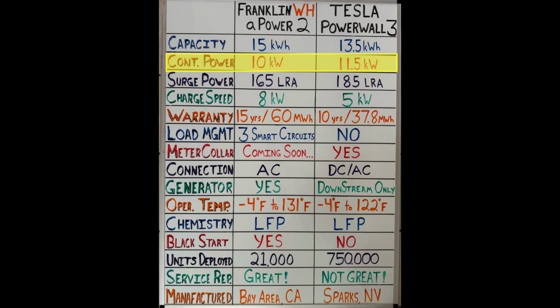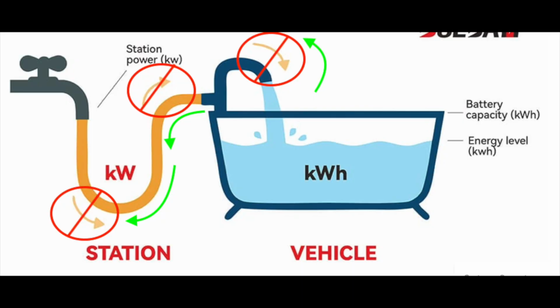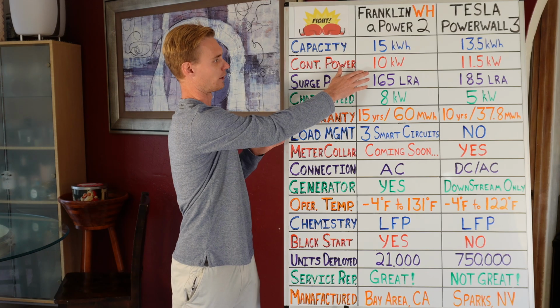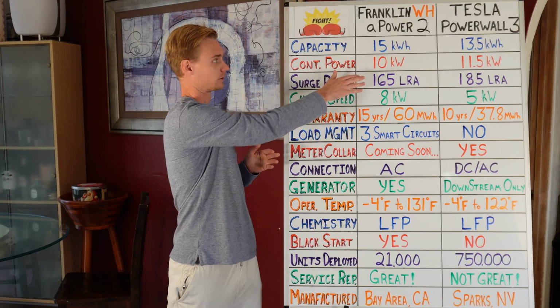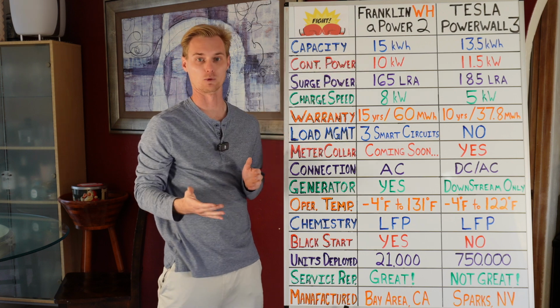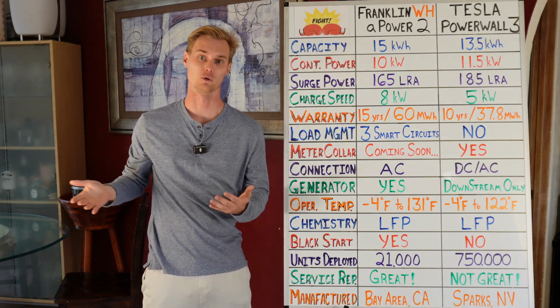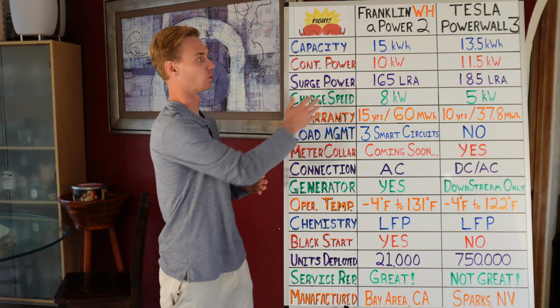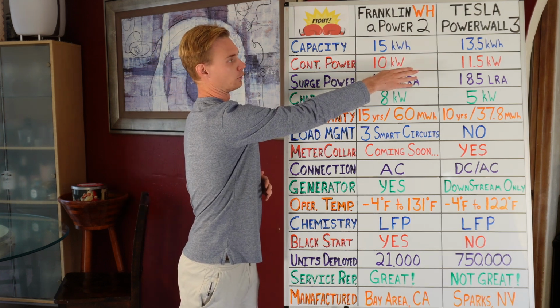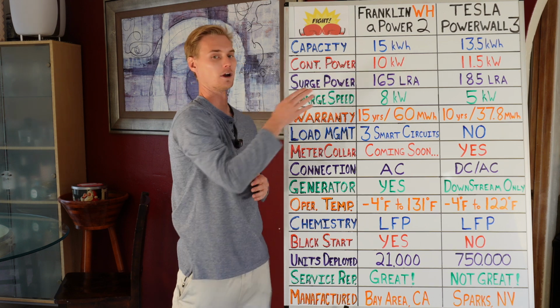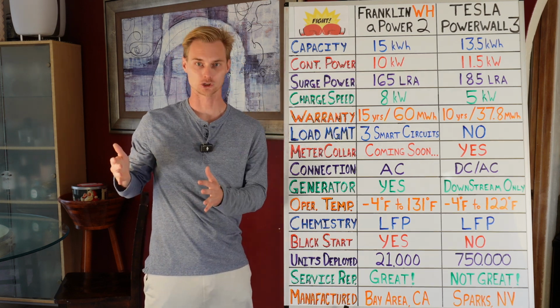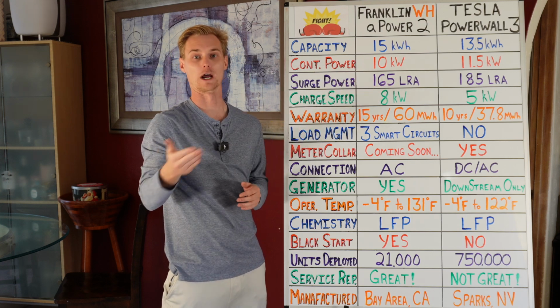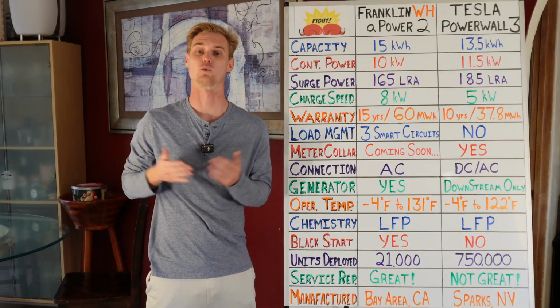Now, continuous power - this is like horsepower, how fast the capacity, the kilowatt hours, can be discharged, at what rate. To sum this up: if the Franklin were discharging at 10 kilowatts, it would take exactly 1.5 hours to drain the full 15 kilowatt hours. Over on the Tesla side, it would take just over an hour at 11.5 kilowatts of discharge speed to drain 13.5 kilowatt hours - it would do exactly 11.5 kilowatt hours in 1 hour.